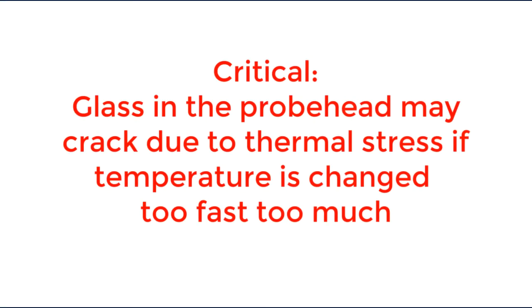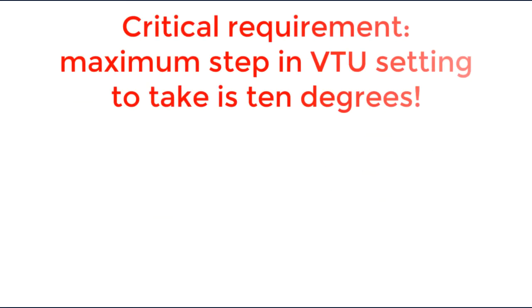When we are changing temperature, we create thermal stress in the glass part of the probe head. If temperature is changed too rapidly, this part may crack and then the probe has to go to Bruker for repair. It is important that when we are ramping spectrometer to specific temperature or cooling it down, we have to take a limited temperature step of 10 degrees and wait at least 3 minutes before the next temperature change is done.